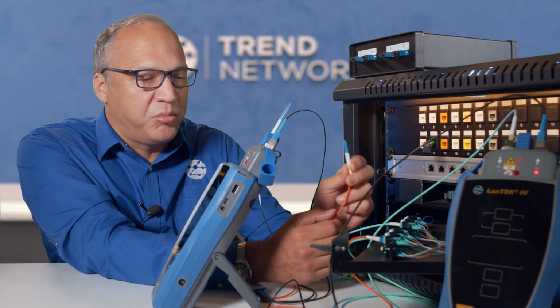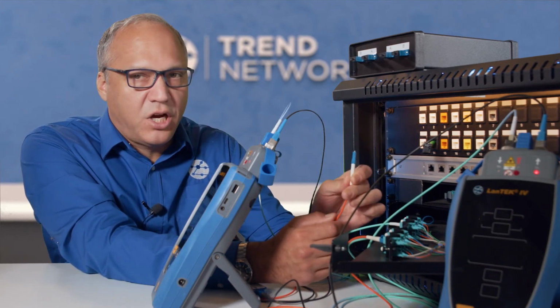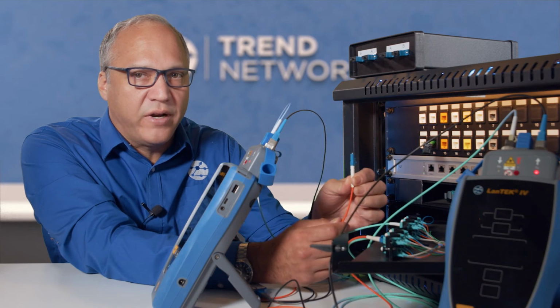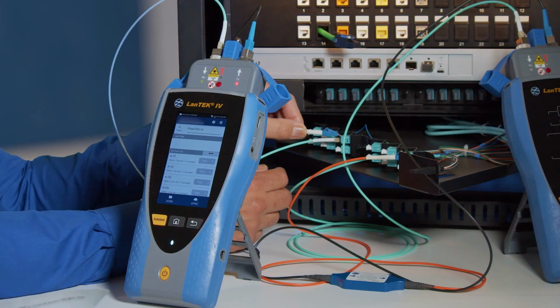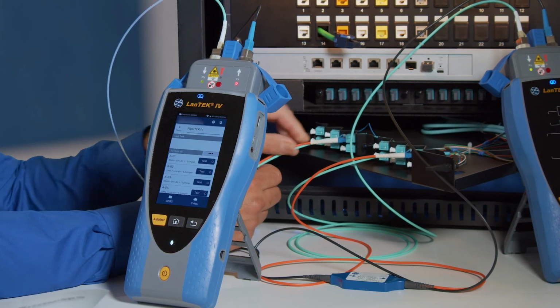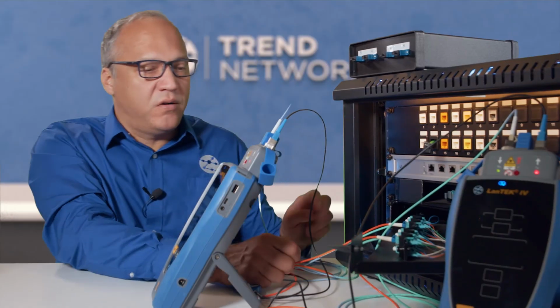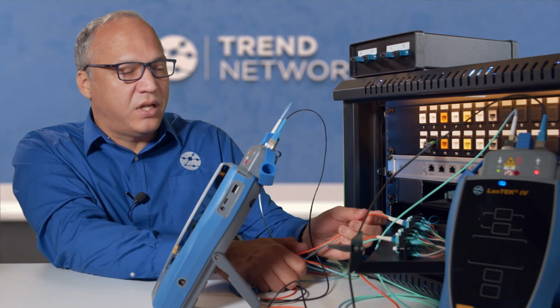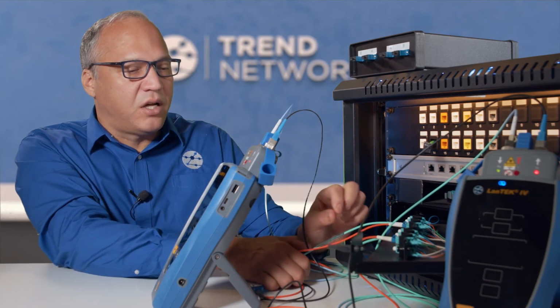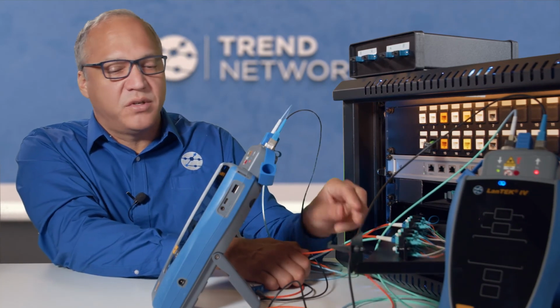So I should hear when I plug in this last cable the chime indicating that the partner finder is working and that my polarity is correct. So I line this up and insert it. And there it is. So there's my chime. So I know my polarity is correct. I have receive on the left on both sides, transmit on the right on both sides.